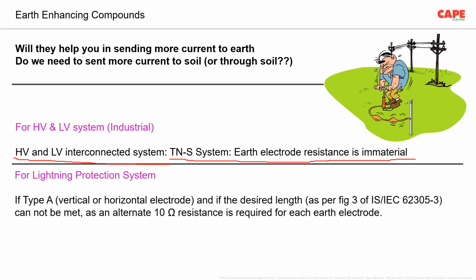Now for the lightning protection system, if type A, lightning protection system earthing is important. In fact, electrodes in soil are important. Lightning protection system earthing is classified into type A and type B. Type A can be a vertical or a horizontal conductor. I have a picture I will show you later on. If you go for a type A earthing, one of the techniques adopted is 10 ohm resistance.